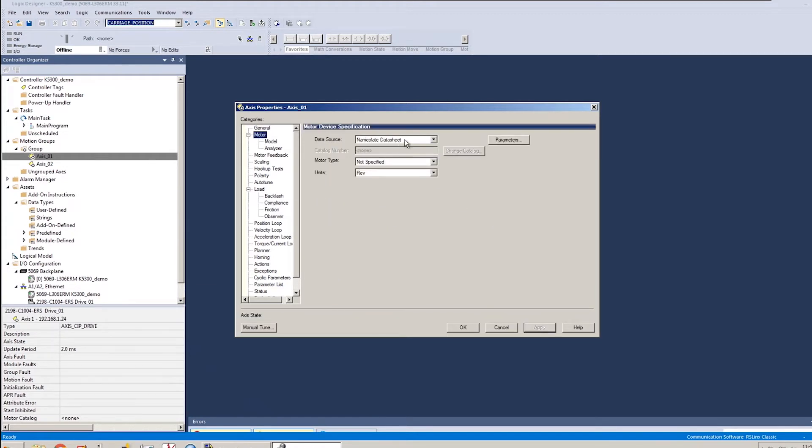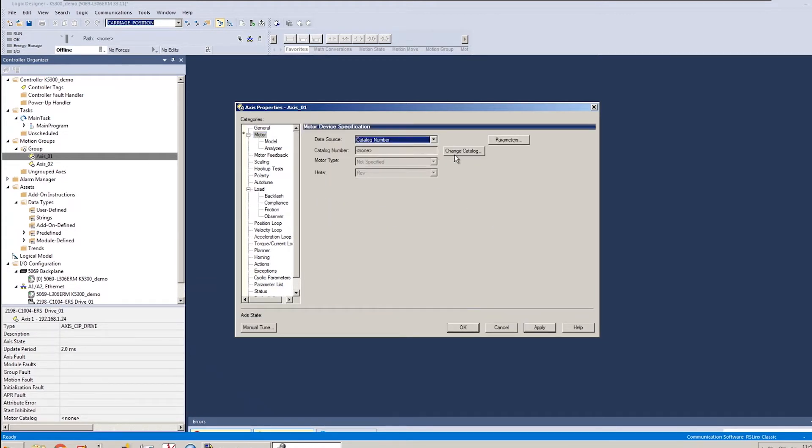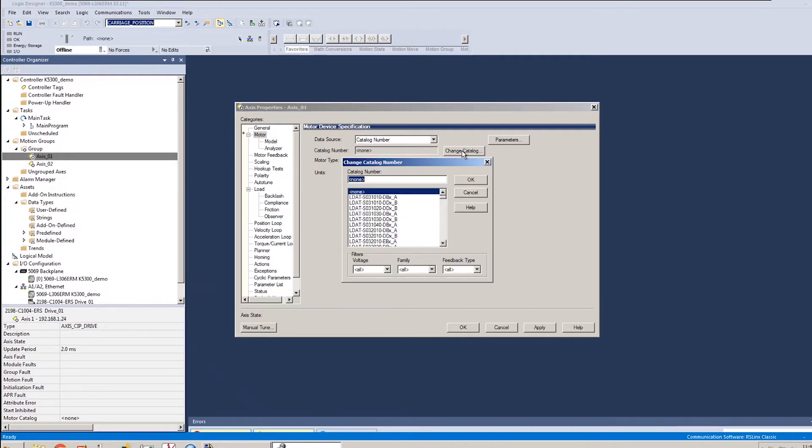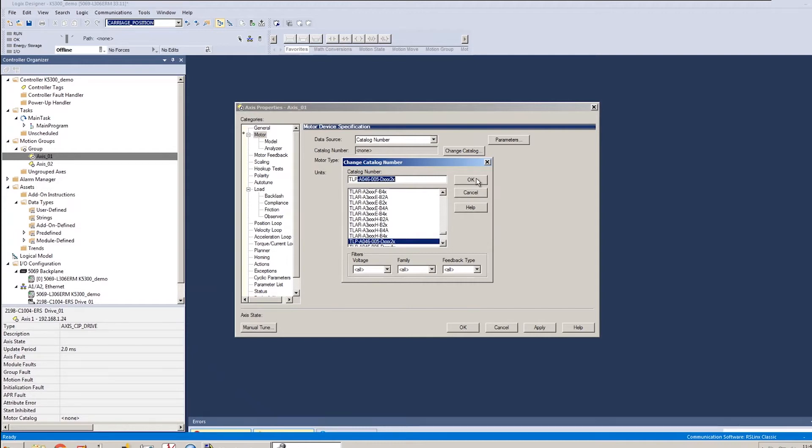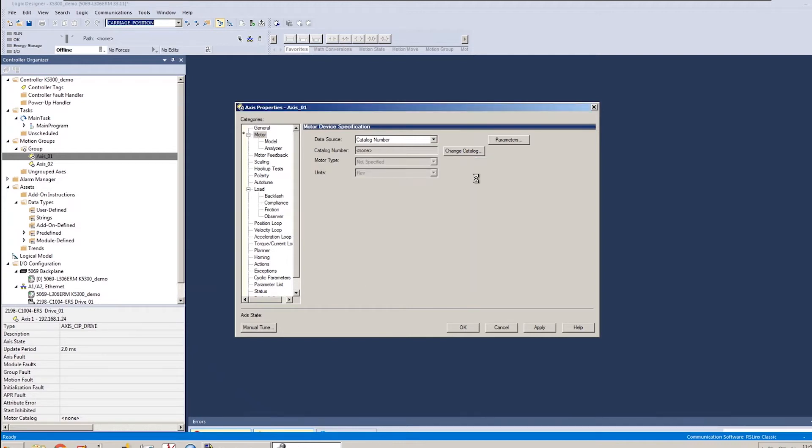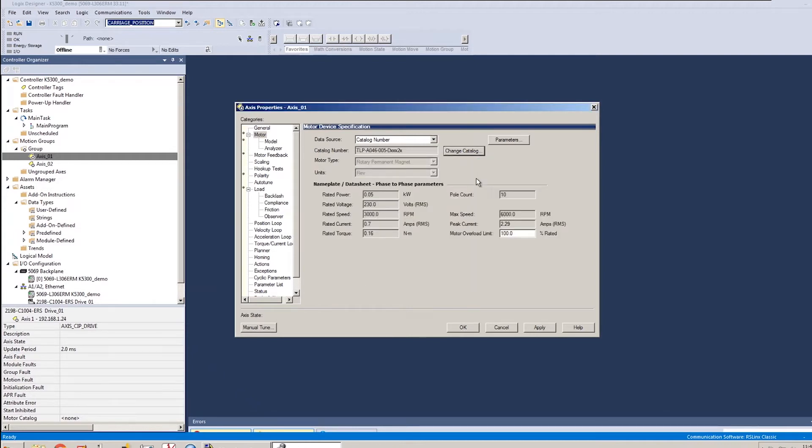It's going to change some other attributes once it's assigned to that drive. The next thing I want to do is go to my motor tab. I'm going to set the data source to catalog number, hit the change catalog number button. And I'm using a TLP-A046 motor today. That's the part number there. I'll assign that. And once that's in there, I'll hit apply.